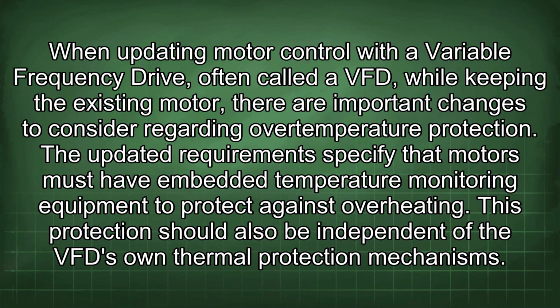When updating motor control with a variable frequency drive, often called a VFD, while keeping the existing motor, there are important changes to consider regarding overtemperature protection. The updated requirements specify that motors must have embedded temperature monitoring equipment to protect against overheating. This protection should also be independent of the VFD's own thermal protection mechanisms.